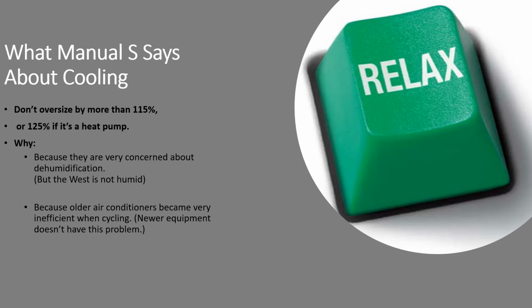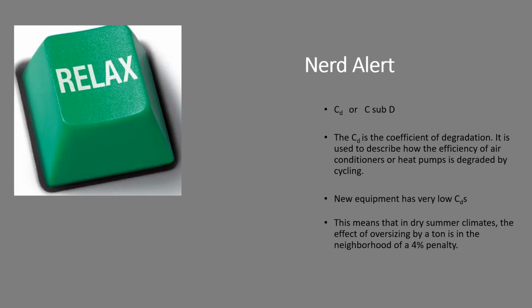Also, older air conditioners had a big penalty for not having long cycles. Newer equipment has improved significantly. The penalty for cycling is something called the C sub D, or the coefficient of degradation. It's used to describe how the efficiency of an air conditioner or heat pump is degraded by cycling. It used to be that C sub Ds would hit you with maybe a 25 or 30% penalty if it cycled. The new ones are much lower than that. A good estimate is that oversizing an air conditioner in the summer by a ton might only get you a penalty of about 4% on energy efficiency. I'm not advocating oversizing.